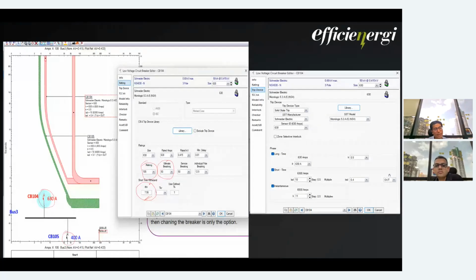I have seen the consultant, even the manufacturer, saying that you take ICW equal to ICU. In many cases, I have seen that when there are no proper documents presented, people say you consider ICU equal to ICW, make a report and submit. But ICU in a real scenario is different. Here also, it will not allow the instantaneous. The maximum tripping or maximum instantaneous will be limited to less than 7.5. In this case, it is just 6930 ampere, which is 6.9 kiloampere.